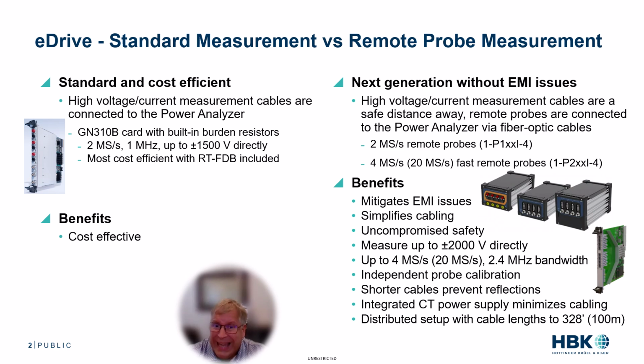We're talking about mitigating EMI issues, simplifying cabling. There's uncompromised safety for both the equipment and you, the user. You can measure up to plus minus 2,000 volts directly. And you can even sample up to 4 million samples per second. In fact, even 20 million samples per second with 2.4 megahertz bandwidth. You've got independent probe calibration capability, shorter cables preventing reflections. There's even an integrated CT power supply on the current remote probe, minimizing cabling. And you can have a distributed setup with cable lengths up to 328 feet or 100 meters.